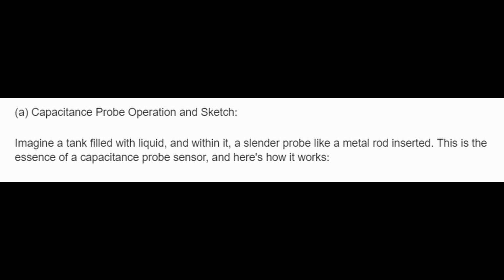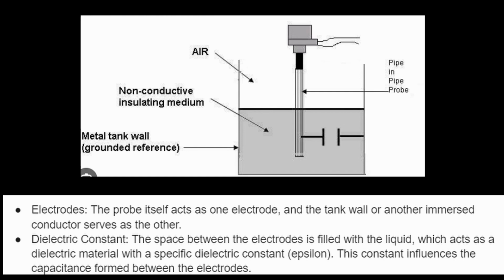A. Capacitance probe operation and sketch. Imagine a tank filled with liquid and within it a slender probe like a metal rod inserted. This is the essence of a capacitance probe sensor, and here's how it works. Look at the sketch. Electrodes. The probe itself acts as one electrode, and the tank wall or other immersed conductor serves as the other. Dielectric constant. The space between the electrodes is filled with the liquid, which acts as a dielectric material with a specific dielectric constant, epsilon. This constant influences the capacitance formed between the electrodes.